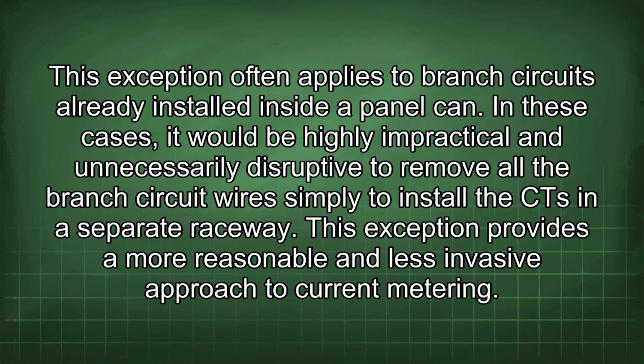This exception often applies to branch circuits already installed inside a panel can. In these cases, it would be highly impractical and unnecessarily disruptive to remove all the branch circuit wires simply to install the CT in a separate raceway. This exception provides a more reasonable and less invasive approach to current metering.